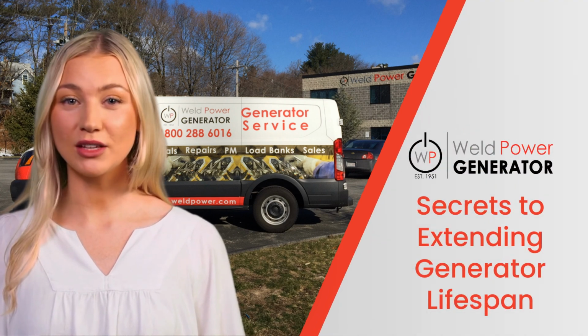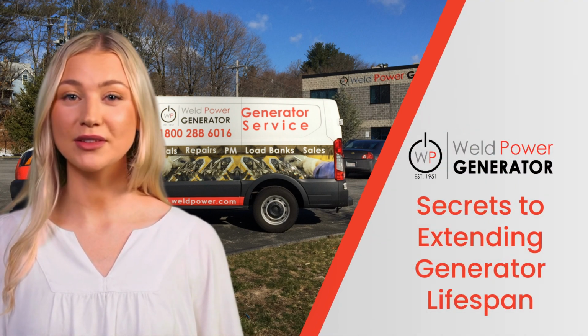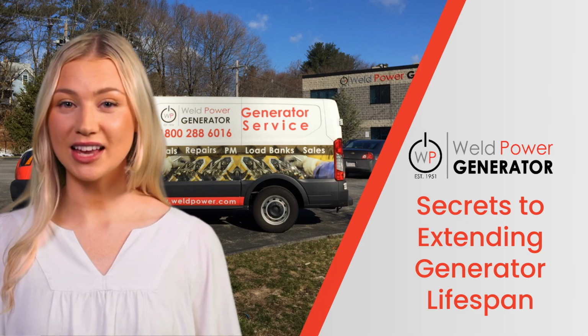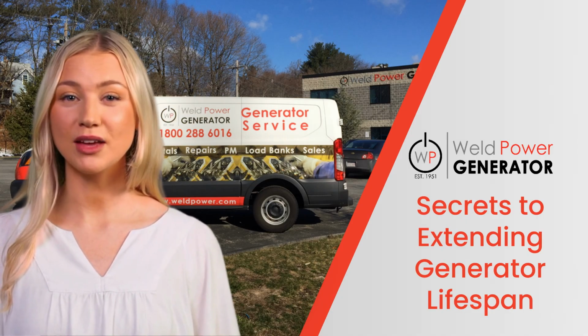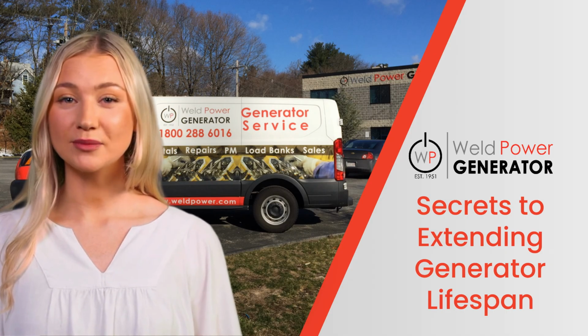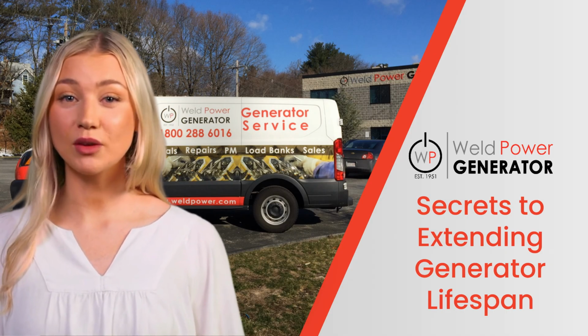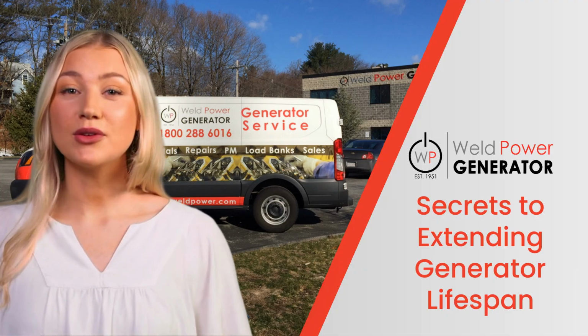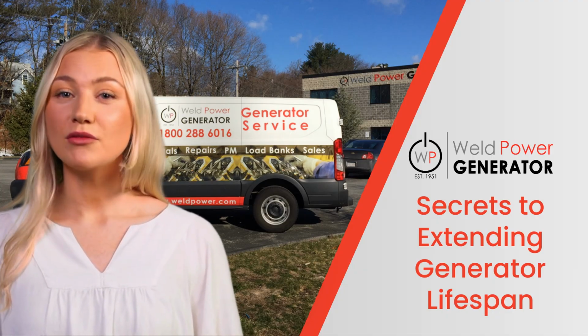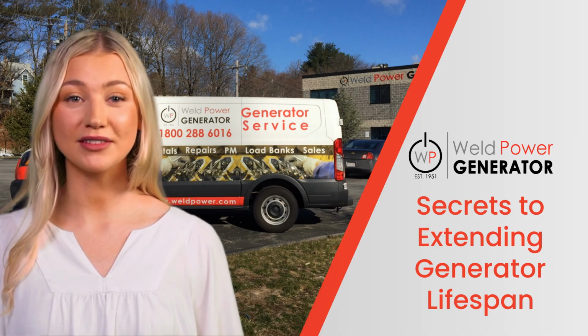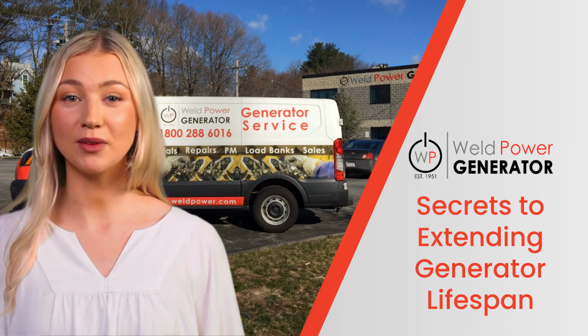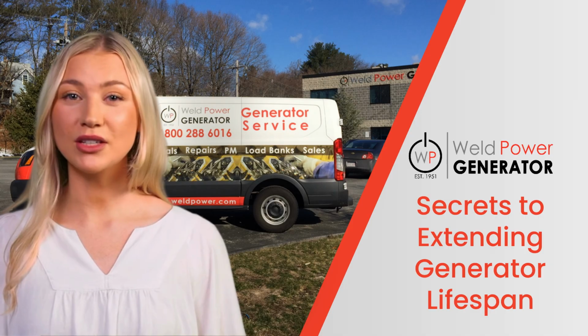There's a reason some generators run flawlessly for 30 years, while others are sidelined after a decade. It rarely comes down to brand or luck. The generator lifespan often comes down to how the equipment is treated between run cycles, and whether the team responsible for it understands that a generator left sitting idle is not a generator at rest. It's a generator in slow decline.